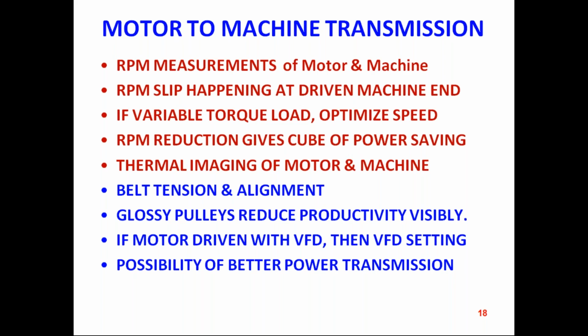Revolutions per minute monitoring, especially in an energy audit, is mandatory now, because we all assume that the motor is giving an excellent RPM, there is no slippage, there is no loss. But practically, having done more than 400 industry energy audits, we find that there is a heavy slippage loss wherever it is not maintained or monitored. The RPM slip is happening, and if it is a variable torque load, we have to optimize the speed.